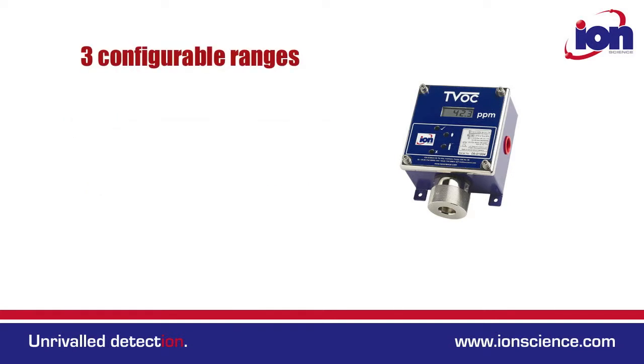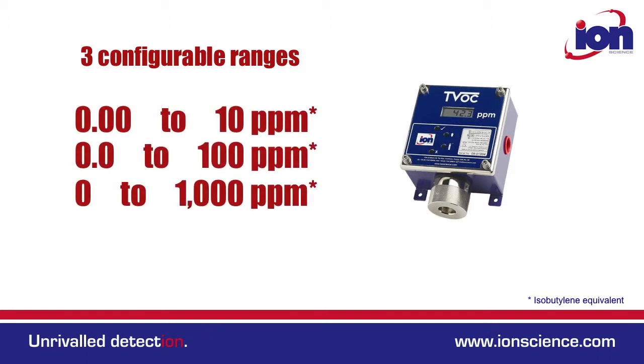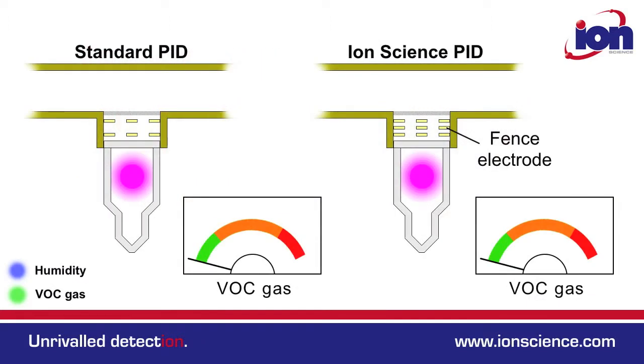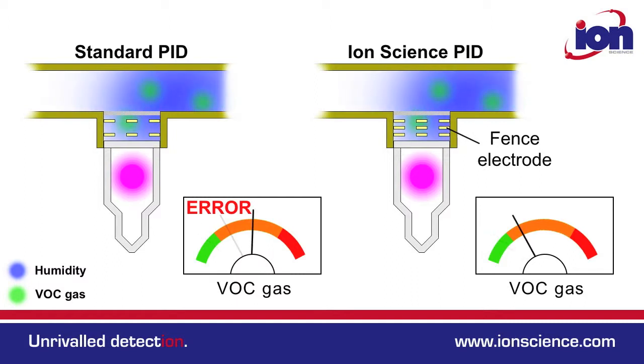This one instrument has three configurable output ranges: 0-10, 0-100 and 0-1000 ppm. All Ion Science instruments have patented fence electrode technology and TVOC is no exception. The fence electrode minimises the effects of humidity, so avoids the need for humidity compensation.